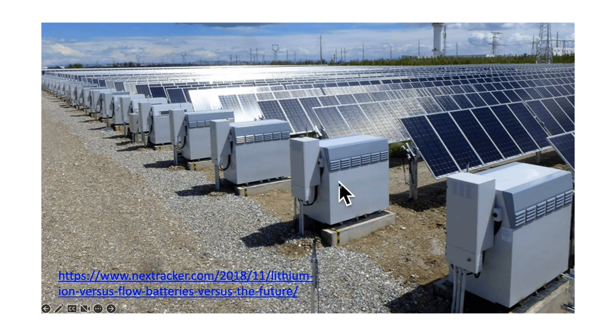So one of the benefits of these flow batteries is that you can discharge it to 0, charge it to 100%, and it doesn't affect the life of the battery at all. And so with lithium ion batteries and lead acid batteries, you can't do that. You can't go from 100 to 0 as often as you want, or it would reduce the life of your battery. So there's a single axis tracker. That's the most common type of utility scale system that there is. Nextracker is the big one too, the big company. So it's kind of neat.